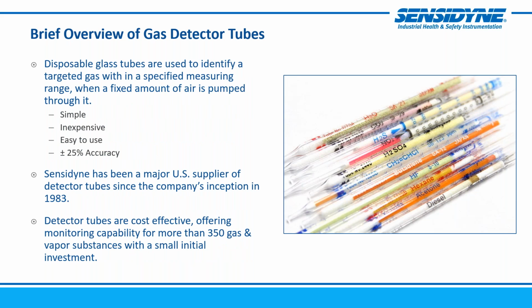So talking a little bit about what is a gas detector tube. These are disposable glass tubes. They're used to identify a targeted gas within a specified measuring range. And the important takeaways are that they're very simple to use and read. They're inexpensive. And that the accuracy, again, it gets you close. It's within the ballpark, but it's not a precision type of instrument. So you have to have that knowledge of it and really how to read them properly to get the most accuracy out of them.